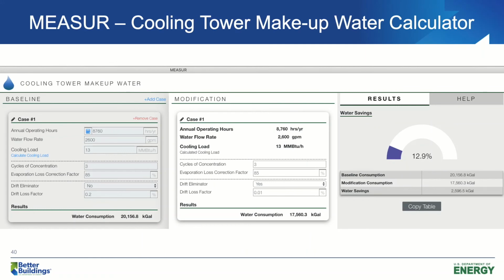The third calculator is cooling tower makeup water calculator. This calculator can help you to quantify the water savings from installing drift eliminators and changing the cycles of concentration. You will need water flow rates and cooling loads to do the calculation. The makeup water savings is shown on the right hand side, both absolute savings and percentage saving numbers.